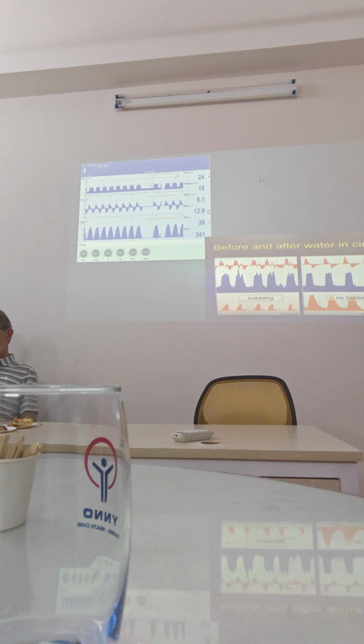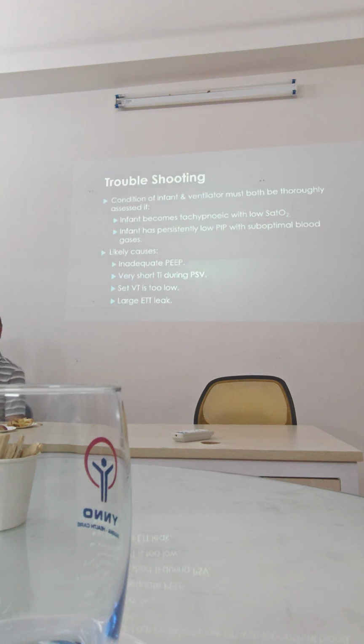And the way you manage auto-triggering is, first of all, you empty the water out of the circuit, and you can see the difference the water being emptied out of the circuit makes to the flow pattern. If that still doesn't fix the auto-triggering, you then have to change the flow sensor, because it probably means the flow sensor is dirty or wet. So let's look at just some troubleshooting with problems related to ventilators and babies.